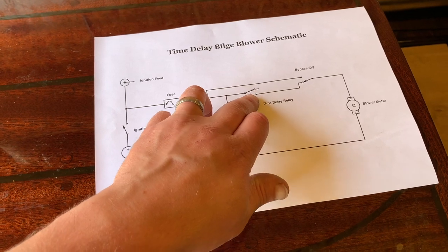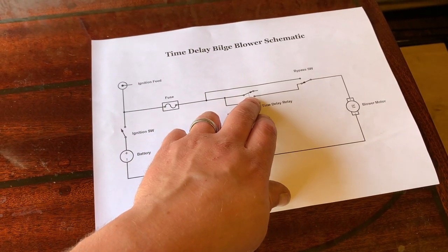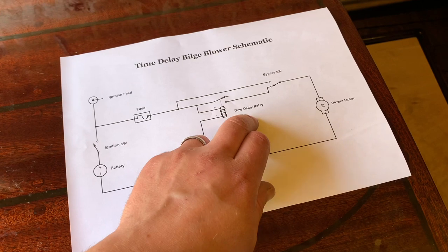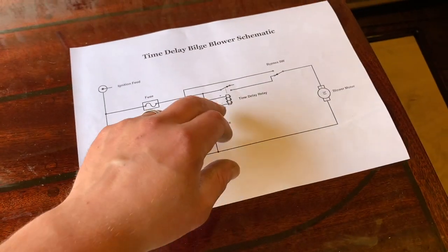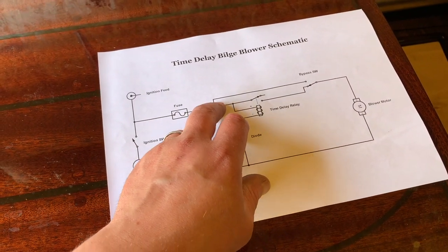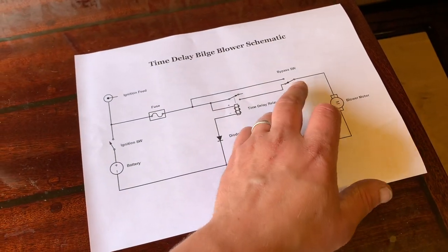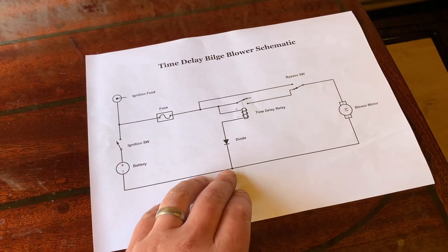You've got the normally open contact there, so when the relay becomes live it sends power through and turns your blower motor on. Once the timer's run out it goes back to normally open. If you want to bypass that, this just pulls the live from the other side of the relay and runs the blower permanently. So you've basically got those two modes — either on a timer then off, or running permanently.